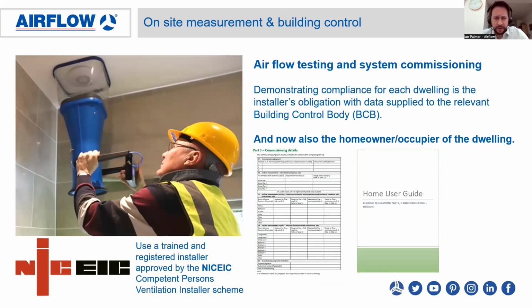So we've got a reference to NICEIC here. So use a trained and registered installer approved by the NICEIC competent persons ventilation installer scheme. They will have been trained to install these types of systems, and it's important to get them tested once installed as well, to check that the ventilation systems are running. And you will know that if your ventilation system has been checked, because you will have been supplied with the commissioning details, which would detail the performance of the ventilation systems.